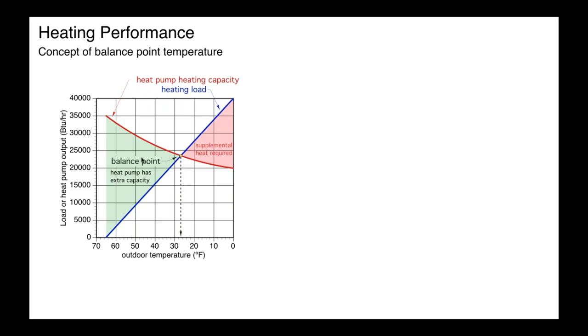So to the left of the balance point, the heat pump actually has more capacity than it needs to heat the building. So it's going to cycle on and off, or some of the newer heat pumps would reduce compressor speed and modulate down on capacity. And it simply means we have the ability to produce heat at a rate greater than what the building needs. Perhaps we could divert some of that heat to another load like domestic water heating. To the right of the balancing point, you've got the opposite condition. The load exceeds the output. So we need some form of supplemental heat.